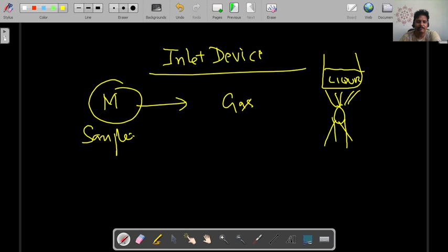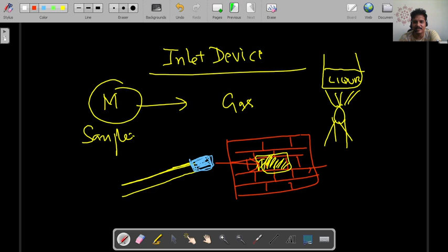Some of the methods use a probe. At the end of the probe, you will load the sample. This is basically for substances which are non-volatile. You load the substance at the tip of it, and you will have a furnace. You just insert this particular probe into this cavity. This is essentially a furnace. The probe contains the sample, and the sample is inserted into this furnace area where it is converted to a gas. This kind of thing is called a direct insertion probe. By this method you will be converting your sample into a gaseous state. There are multiple methods available, but we are restricting here to a single method by which you can convert your sample into gas.